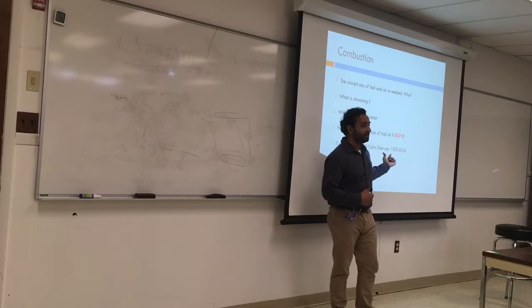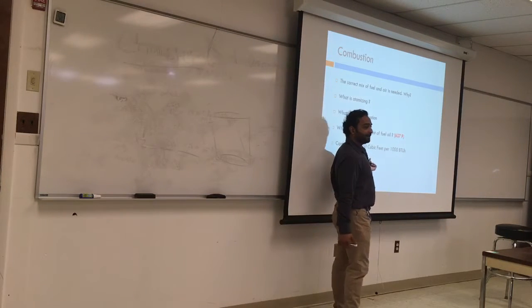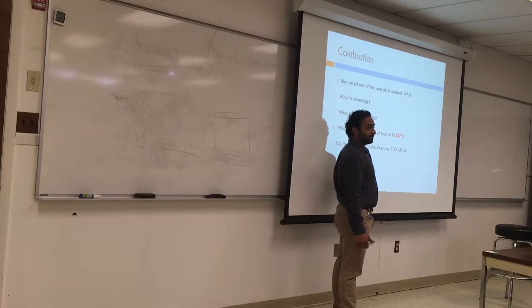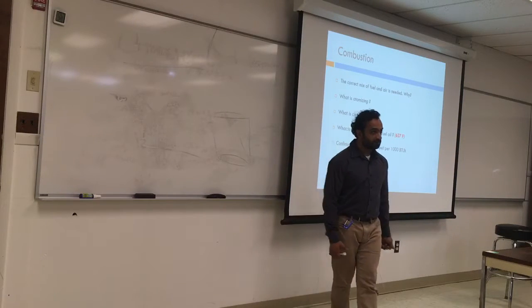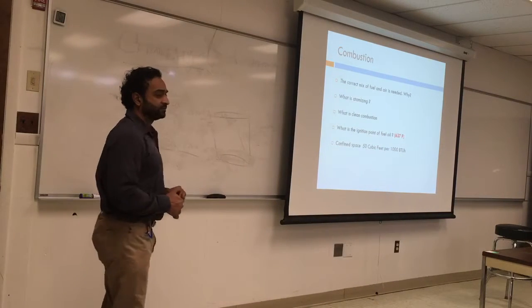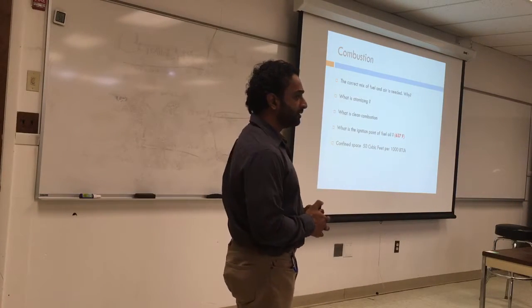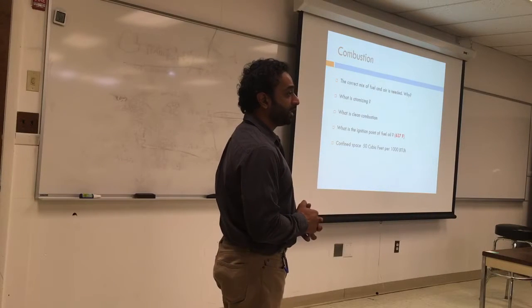If you have anything more than 50 cubic feet per 1,000 BTU hour of combustion, that is not confined space. Less is confined space. So if I have only 49 cubic feet for 1,000 BTU, that's a confined space. Any more is not confined space. And if more, it doesn't go through the code, right? It's not the code. You cannot have less than.